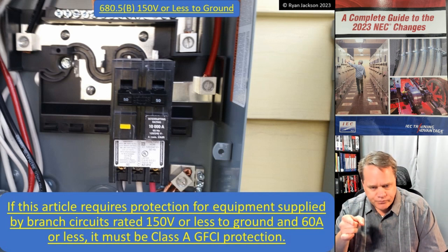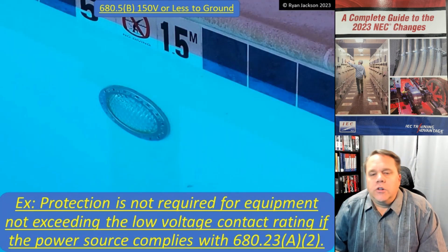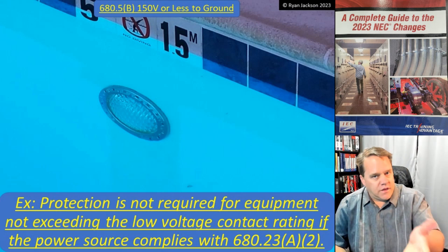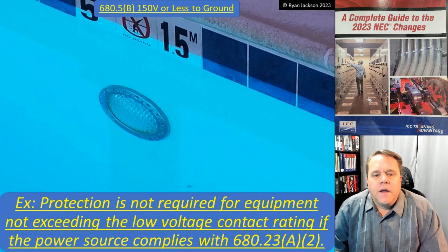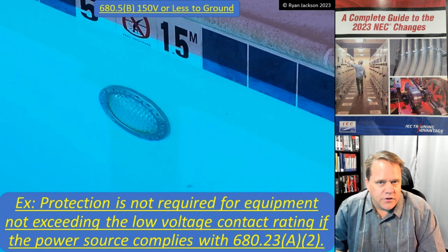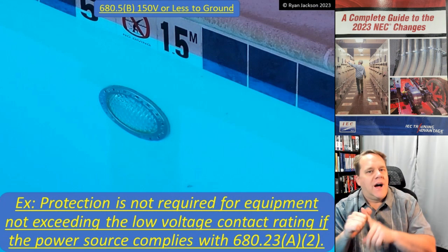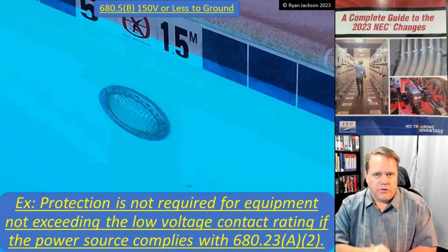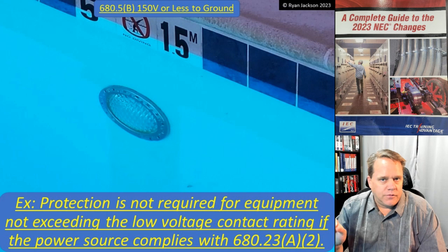So to read this one more time: if the circuit is 150 volts or less to ground and 60 amps or less, then you need Class A GFCI protection. Now looking at the photograph, if we have underwater swimming pool lighting, generally speaking that needs to be GFCI protected. However, the exception says protection is not required for equipment that does not exceed the low voltage contact rating per Article 100, if the power source complies with 680.23(A)(2). So if you have low-voltage lighting from a swimming pool isolating transformer with very limited energy output, you do not need GFCI. If the luminaire is 120 volts, you need GFCI; if it's below the low-voltage contact limit from a swimming pool transformer, then you don't.